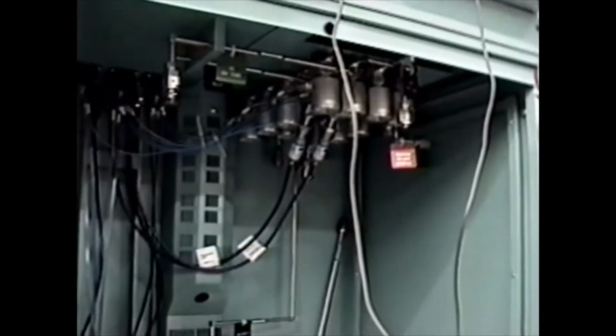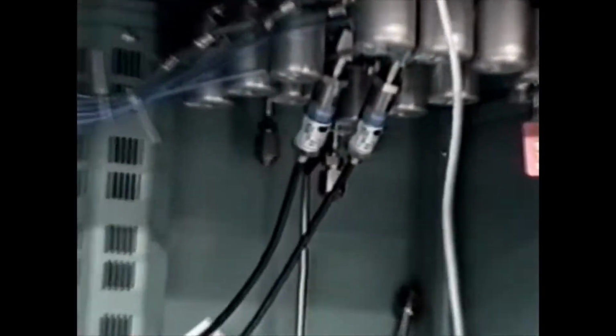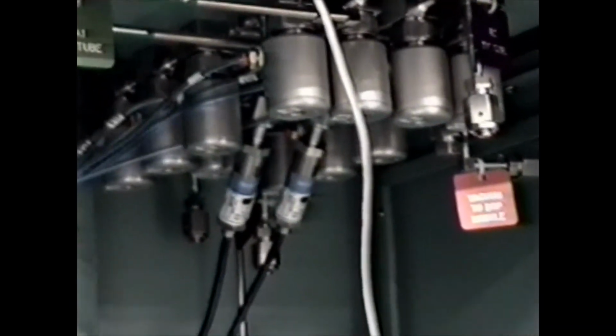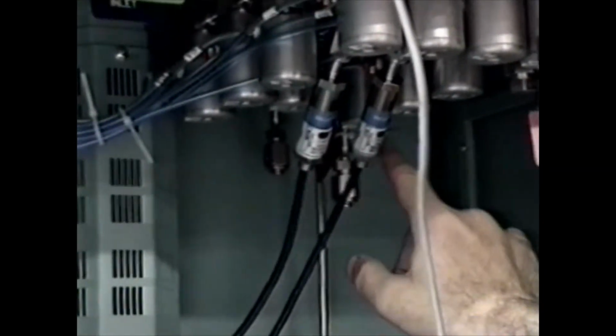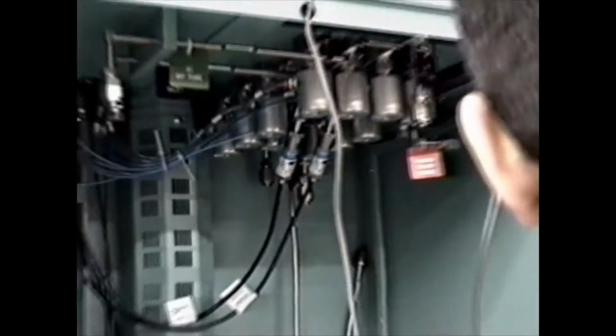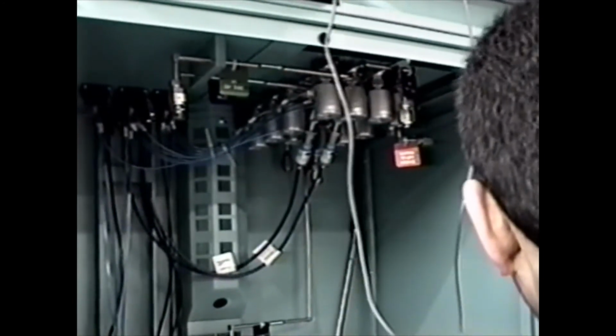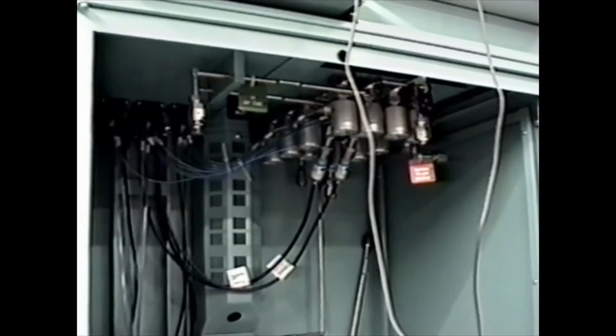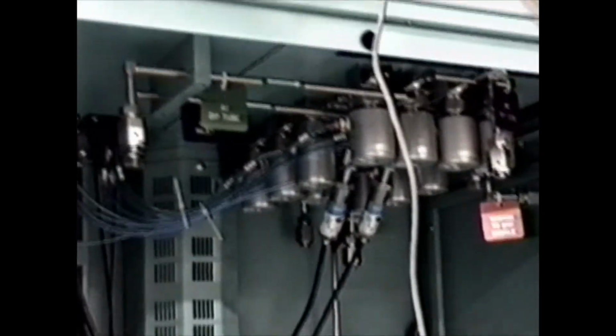Then the two transducers over here have two pots on them. Z for zero, S for span. Yep. Okay? With the vacuum on, you adjust the zero pot on both of them to read within the range that I gave you, 76 to 91. Okay? Then, once it reads that number, you go and you close V8, V9, and V29.